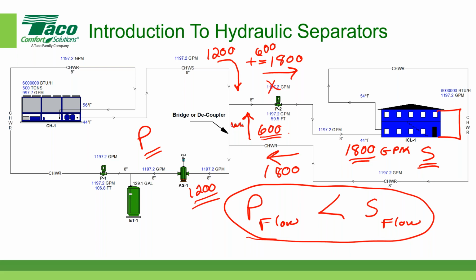And obviously that does affect the temperatures as well, especially in this case. I'm not going to put an exact number in there, but let's say this was 44 degrees Fahrenheit on the primary side, and the secondary side in this case is coming back at 54. If you have 54 degree Fahrenheit water at 600 GPM mixing with 1,200, then the water temperature coming back here, I'm not going to do the calculation out, would be higher than 44. I'm just going to arbitrarily pick a number. It's not the right number. Maybe the mixed temperature is somewhere around 47 degrees. Maybe it's in that order of magnitude.